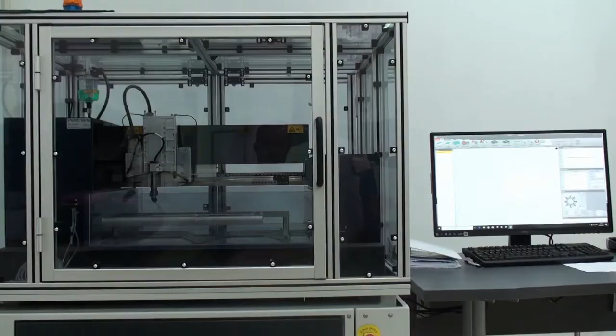This is a confocal scanning acoustic microscope, also known as CSAM, from the company PVA Tepla, model number SAM301. CSAM uses ultrasound waves to detect changes in acoustic impedance in integrated ICs and other similar materials. It can be used for analysis of samples in the ultrasound frequency range up to 400 MHz. It is designed by default for a transducer, and is equipped with a graphical user interface for ease of operation and flexible applicability. The sample bath and scanner can be adapted to custom requirements.